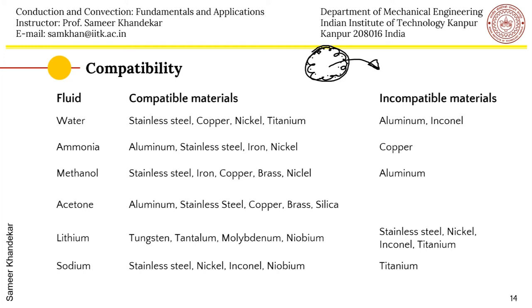During this time, the idea is that this fluid should not react with the porous material and form some gases which are harmful for the heat transfer to take place. So if you are using water, then one can use stainless steel or copper, nickel, titanium. But if you use aluminum with water, then the aluminum will react, it will oxidize, and form aluminum oxides, and hydrogen gas will be generated inside this heat pipe. This hydrogen gas will hamper the heat transfer, because it will collect in the condenser area, which is the coldest part of the whole device, and it will block the condenser.